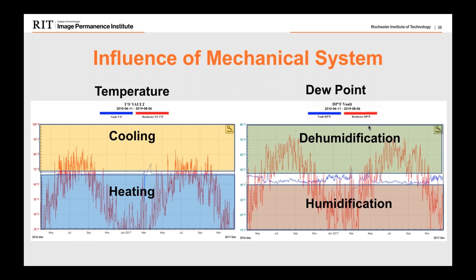It's also possible that the data you look at is not attributable to intentional work by the mechanical system, but can result from loads on or in the space. This is one we see very often, and it's a pretty consistent pattern tied to someone's work schedule. Someone comes into the space, probably turns on the lights, might prop open the door for easy access or to talk with colleagues, or opens up shades to make their work environment more pleasant. We see temperature gain for 5 days a week, dropping back down overnight and on weekends. So it's important to critically examine the spaces to inform what we're seeing in the data, that this isn't a mechanical system issue but has to do with the operation of the space itself.